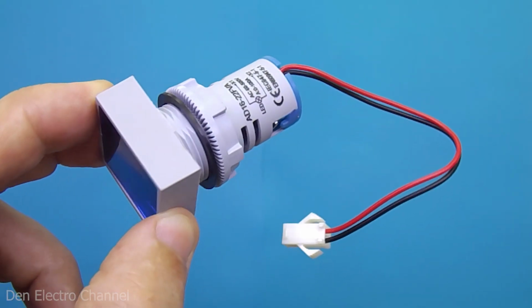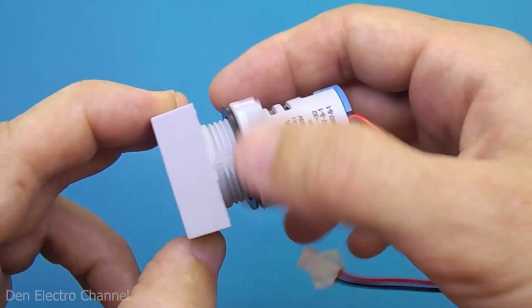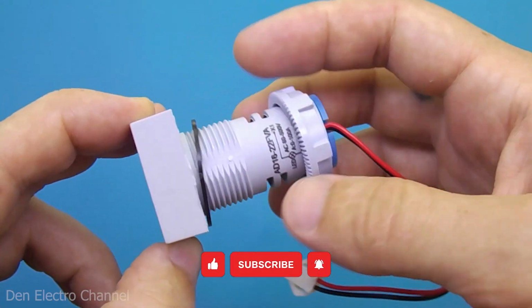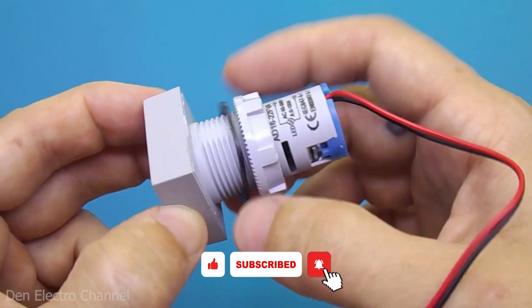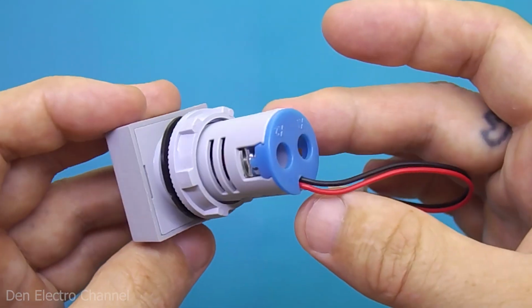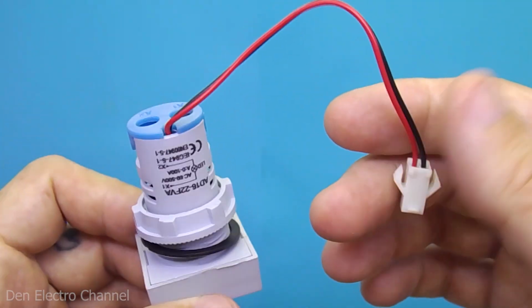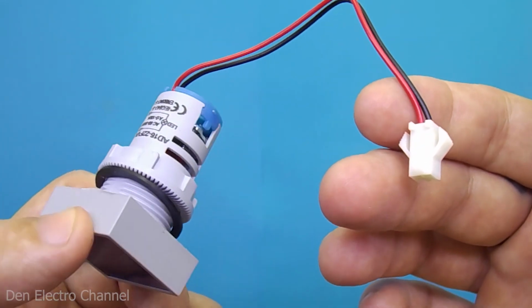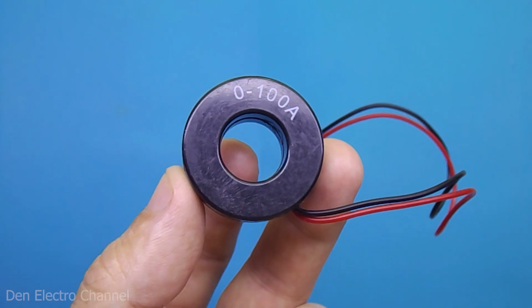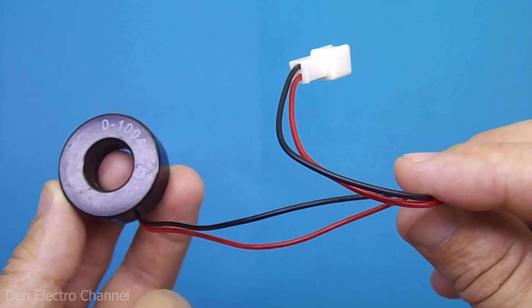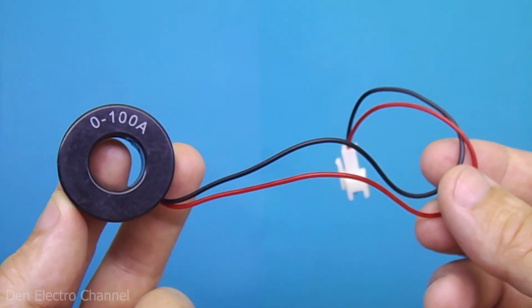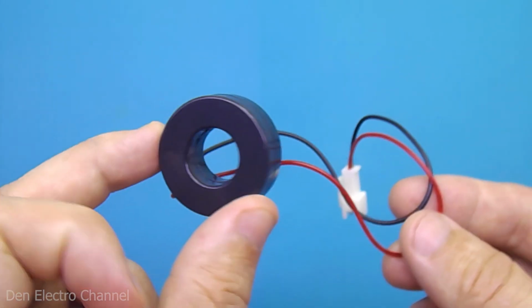This type of voltammeter is usually installed in electrical panels. A large hole is made in the wall of the panel, then the voltammeter is inserted and tightened at the back with a nut. At the back there are two terminals for connecting the AC power supply, and thin wires with a connector for the current transformer. The current transformer contains a round metal core, with a coil of many turns wound around it.